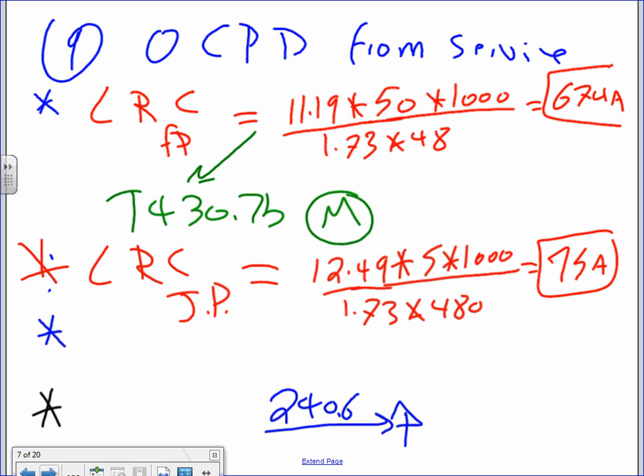Does that make sense? So you find the full load current for both of these. Find the full load current for both of them. Then the second step is add them up. 674, you need to add them up, plus 75. That will give me 749 amps. Add them up.